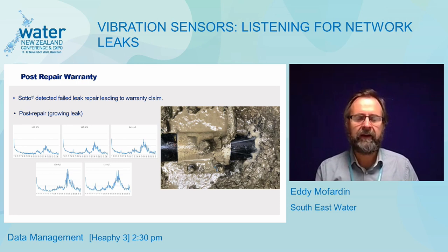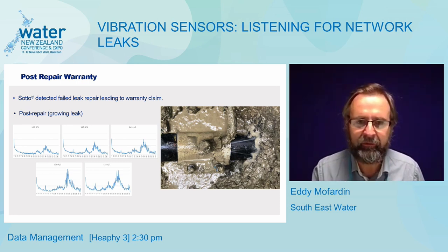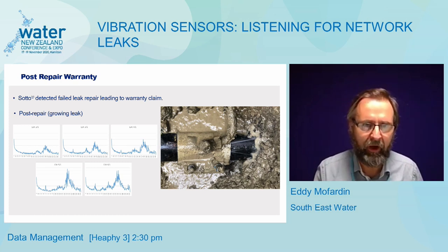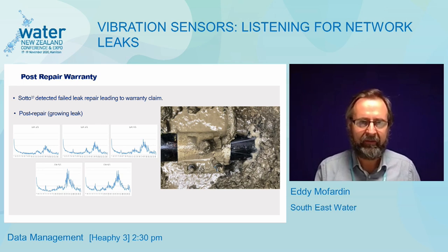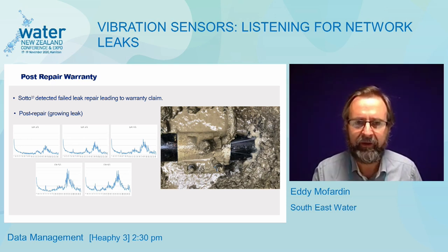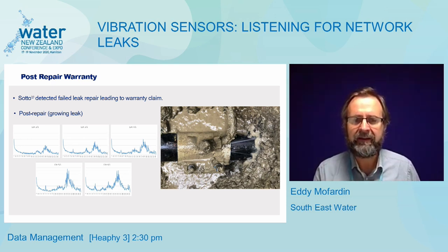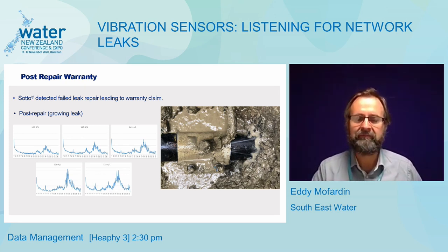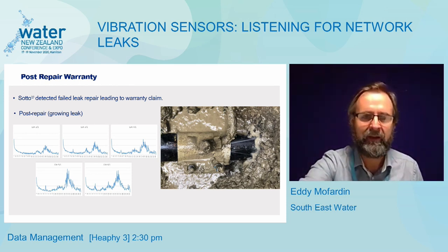At another site, after the leak was repaired I expected the vibrations to disappear, but instead over five successive days the vibration signal grew stronger and stronger. I reported this to our operations group and they sent a crew back out, dug up the repair work, and discovered that the clamp bolts had not been tightened properly. The image clearly shows the leaking repair. Sotto effectively allowed us to make a warranty claim on the repair work — another benefit we had not expected.